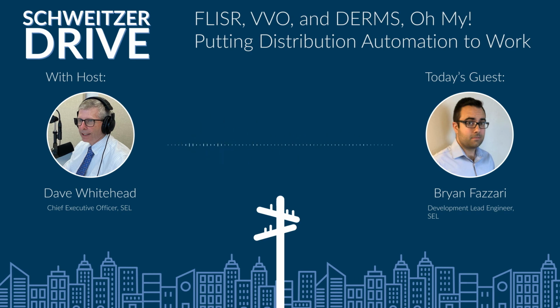The goal of a FLISR system is to communicate with every recloser, switch, and breaker on that circuit, and on every adjacent circuit, and figure out: is there a way to isolate that fault better? Can I open a downline switch and backfeed power from another feeder to restore some of these customers? That's what FLISR is looking for.